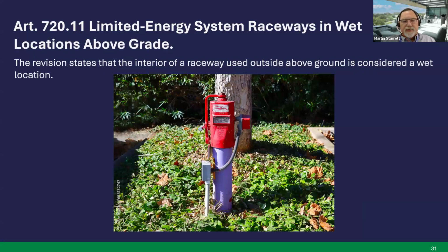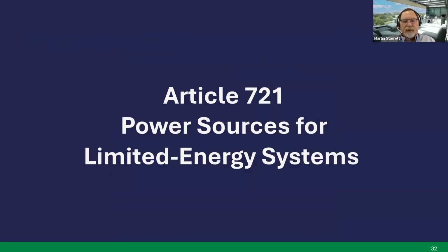There's a whole bunch of changes, but one change, 720.11, limited energy system raceways and wet locations above grade. The revision states that the interior of a raceway used outside above grade is considered a wet location. So any of the cables that you install in a raceway outside would have to be suitable for a wet location. Next slide.